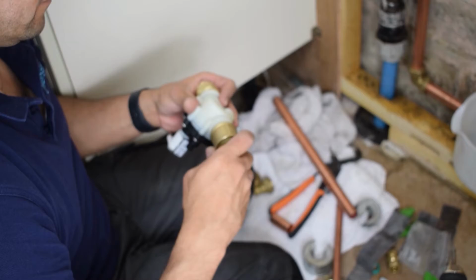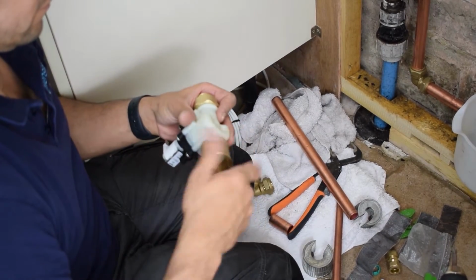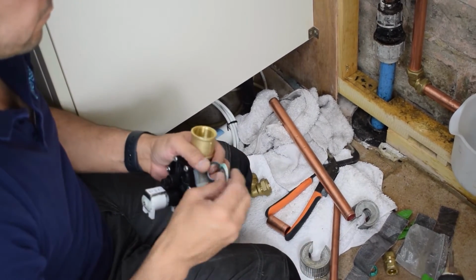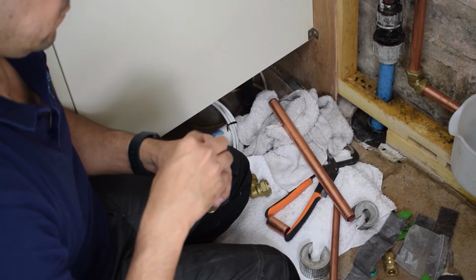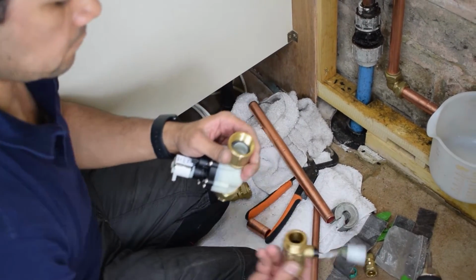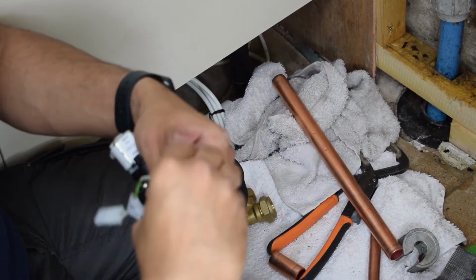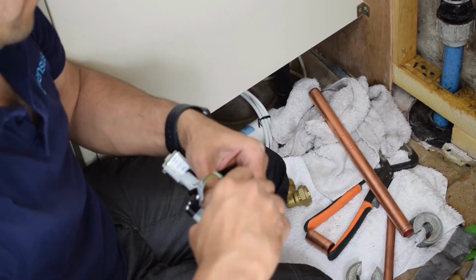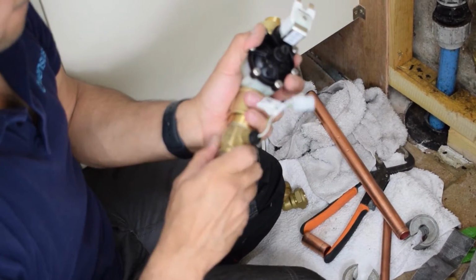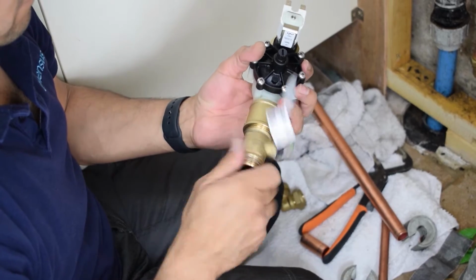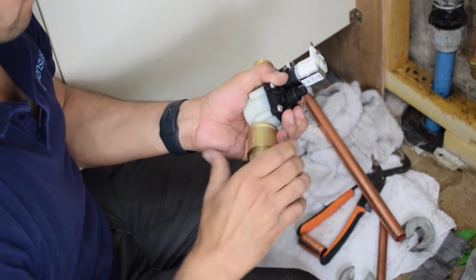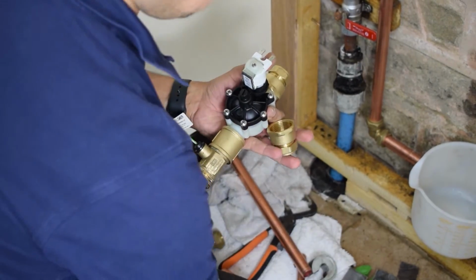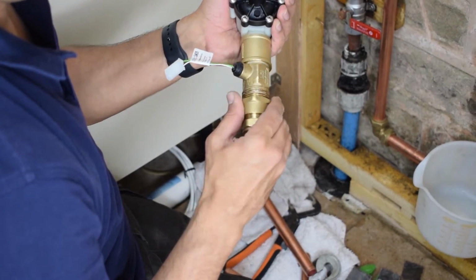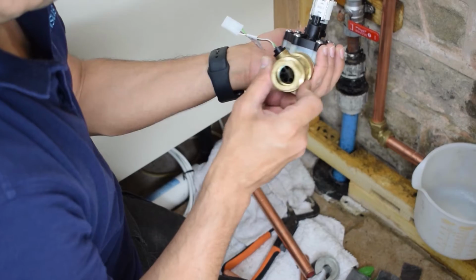So it's going up. And we're going to put the flow sensor before the valve because the flow sensor works better when there's a bit of straight pipe before it and the valve acts as a bit of a bend. So again, there's a flat edge on that valve, so put a few washers in before putting the flow sensor in. So again, there's a flat edge on the flow sensor, tighten that up so that both flat edges join and those washers again maintain the water tightness. Again, a washer's in between the fitting and the flow sensor.